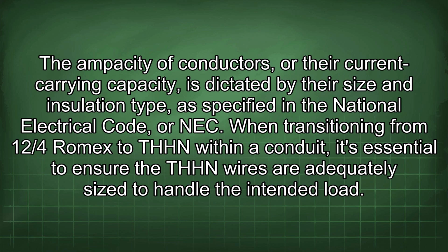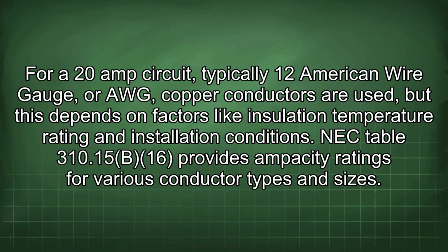When transitioning from 12/4 Romex to THHN within a conduit, it's essential to ensure the THHN wires are adequately sized to handle the intended load. For a 20-amp circuit, typically 12 American wire gauge copper conductors are used, but this depends on factors like insulation temperature rating and installation conditions. NEC Table 310.15(B)(16) provides ampacity ratings for various conductor types and sizes.